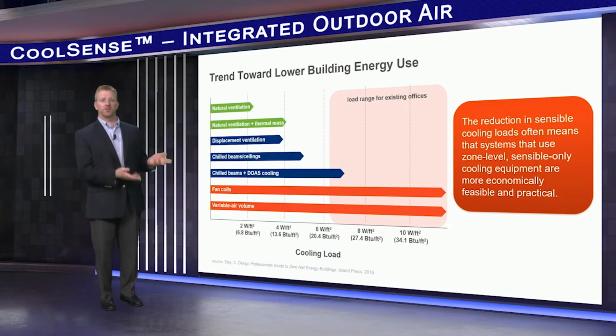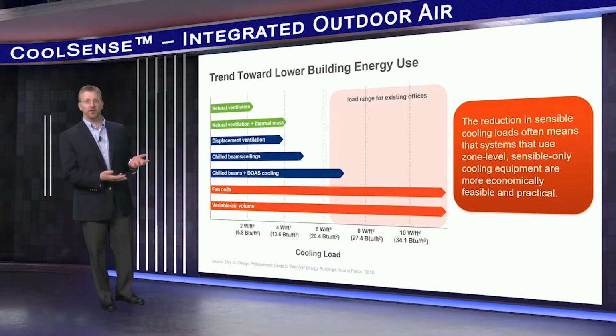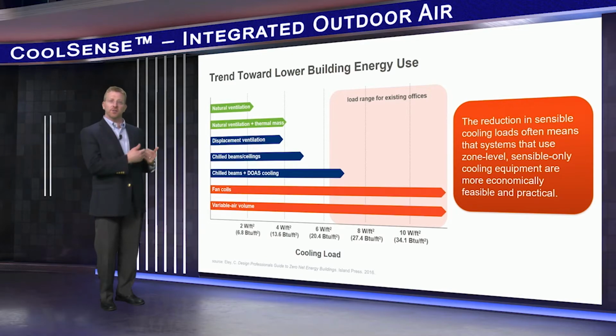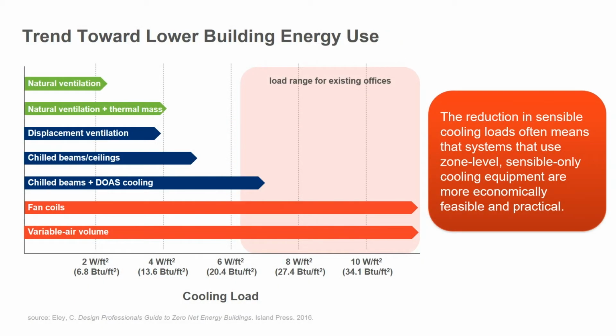Consider this chart from the Design Professional's Guide to Net Zero Energy Buildings. As we look at the buildings with the higher space loads, depicted here, designers tend to favor systems like VAV or fan coils. But when buildings have lower sensible cooling loads, systems that use zone-level sensible only cooling equipment typically become more practical and more economically feasible.